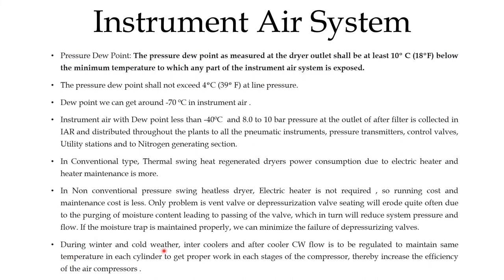During winter and cold weather, intercooler and aftercooler cooling water flow must be regulated to maintain the same temperature in each cylinder to get proper work in each stage of the compressor, thereby increasing the efficiency of the air compressor. If the cooling water is not throttled in the intercooler and aftercooler during winter or cold weather, that will affect the compression ratio. This is the main point to follow for intercoolers and aftercoolers during winter or cold weather.